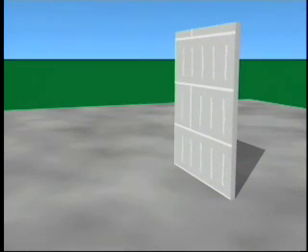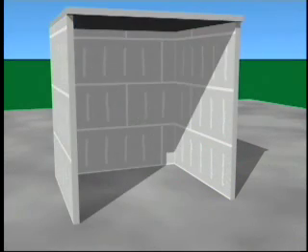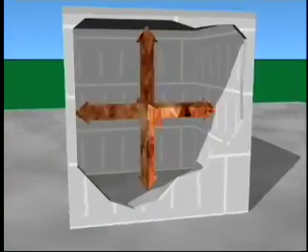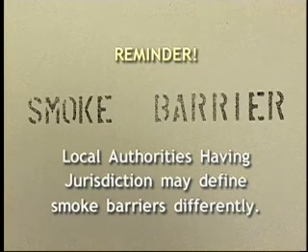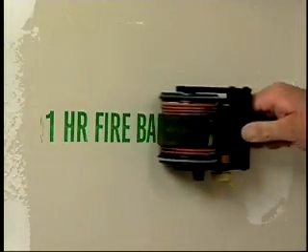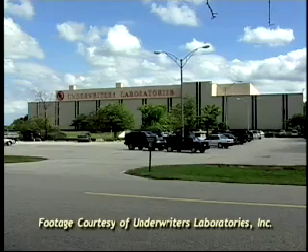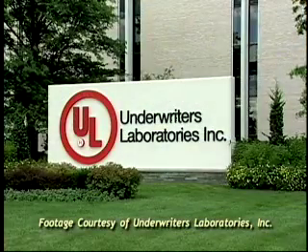A compartment is like a box, made up of a floor, walls, and a ceiling. Each side of the box is known as a fire or smoke barrier. A smoke barrier is defined by the Life Safety Code as a continuous fire-rated wall that extends from exterior wall to exterior wall and floor to floor. Be careful, however, because some local authorities having jurisdiction may define smoke barriers differently. A fire barrier, by contrast, is simply a wall or floor designed to prevent the products of combustion from spreading vertically or horizontally for a specific amount of time, and is tested by a third-party lab to specific ASTM test standards.